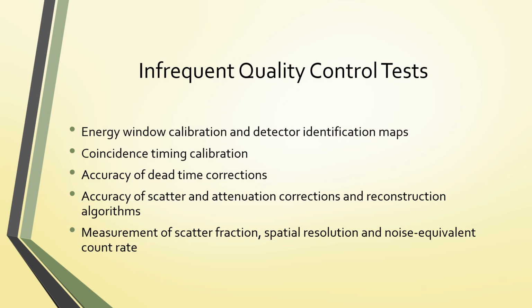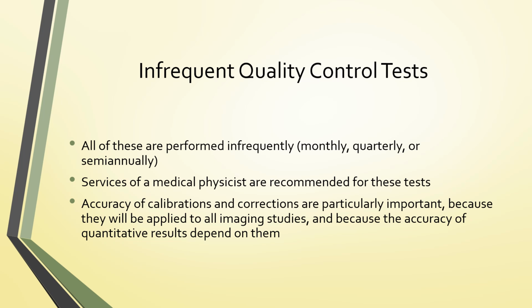Some more quality control tests that are a little less frequently performed: energy window calibration and detector identification maps, coincidence timing calibration, accuracy of dead time corrections, accuracy of scatter and attenuation correction, and measurement of scatter fraction, spatial resolution, and the noise equivalent count rate. So all of these tests are performed infrequently, which means it's either monthly, quarterly, semi-annually, or even annually. And it is recommended to have a medical physicist perform these tests.